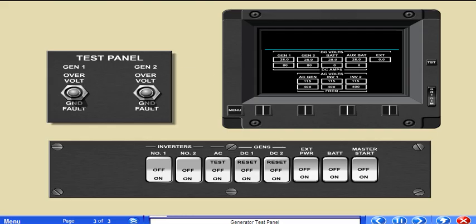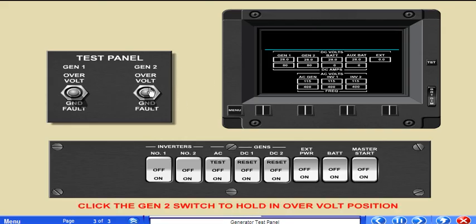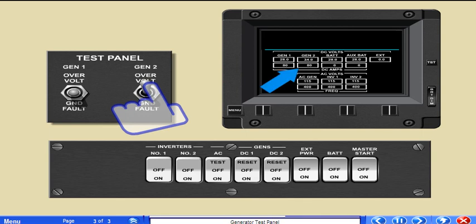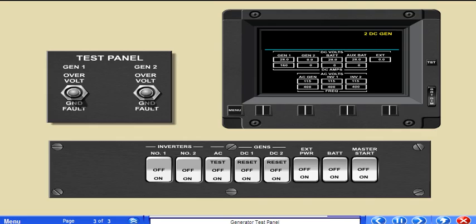Holding either switch to the overvolt position for 5 seconds causes the associated DC generator caution message to illuminate. This indicates the generator has gone offline from the induced overvoltage. The generator may be restored to operation by moving its switch to Reset, then to the on position.